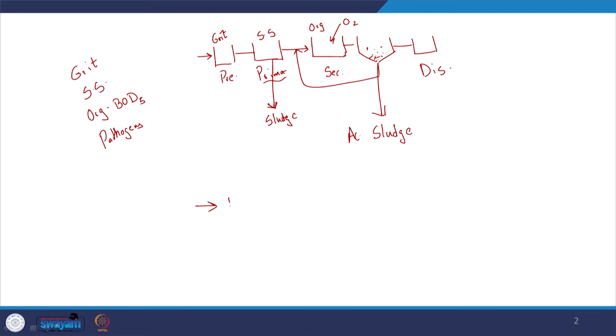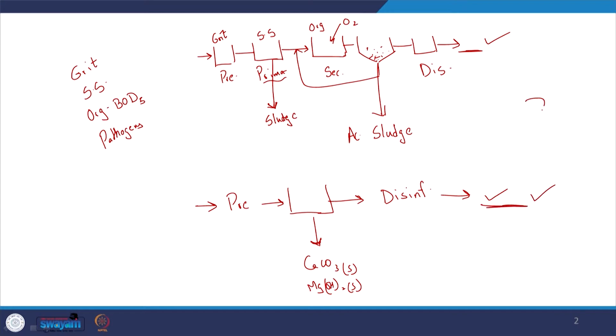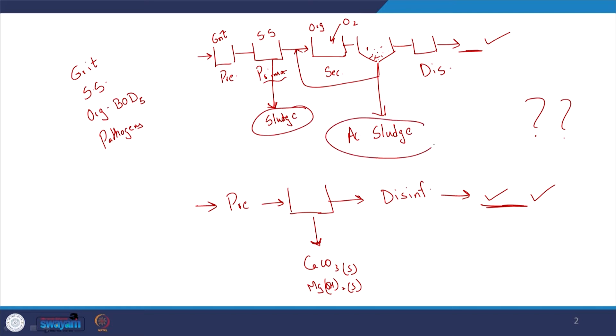And for water treatment: preliminary treatment, primary where we have some sludge being formed, but before that we have coagulation and flocculation. If I have lime softening, that will have its own sludge — CaCO3 is the relevant solid, or magnesium hydroxide. Even during sedimentation and after coagulation and flocculation, I will have some kind of settled sludge, and then I will have disinfection. The water is relatively fit for discharge after wastewater treatment, and fit for drinking after water treatment. But as you can see, during water treatment I am producing sludge — activated sludge and some primarily inorganic-based or relatively inert sludge.